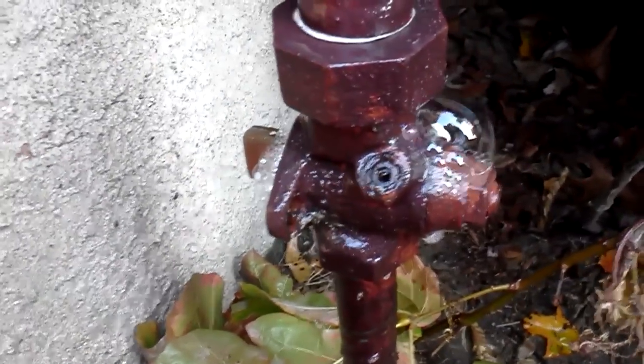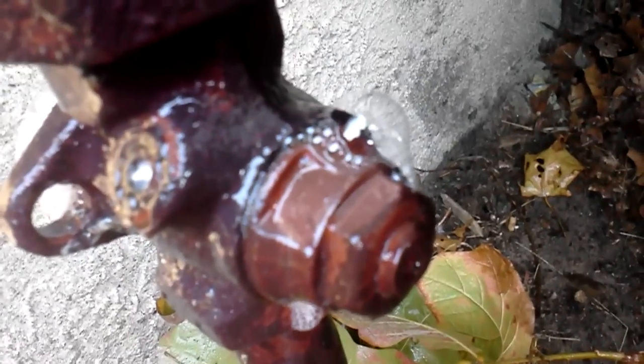That's how you can tell if you have a gas leak. If you're whiffing gas outside, just mix up some dish detergent in a spray bottle of water. Go around, spray all your fittings, look real close, and this is what you'll see — you'll see those bubbles.